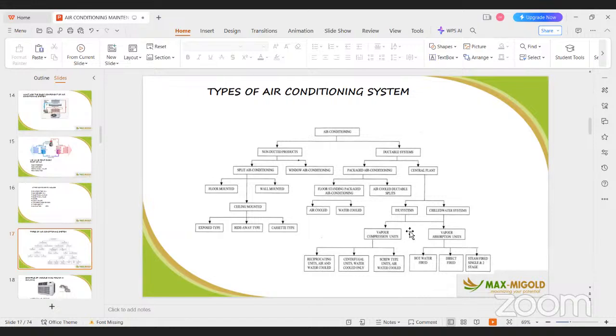But each of them has advantages and disadvantages. Ceiling conceal units are very expensive, and for the water system you need a small pump always built into the AC that takes water from a low level to a high level. The day that pump fails, you have rain inside your office - you create artificial rain, which can impair your performance as an FM and affect the quality of your building structure. So AC units are divided into ductable type and non-ductable type.